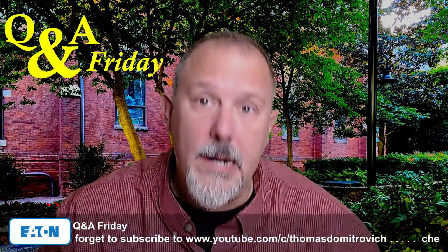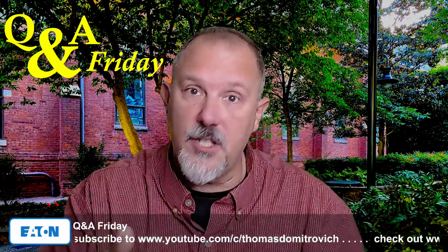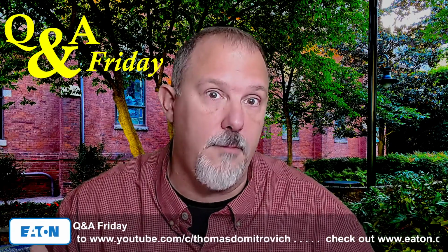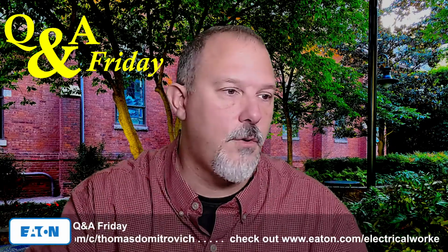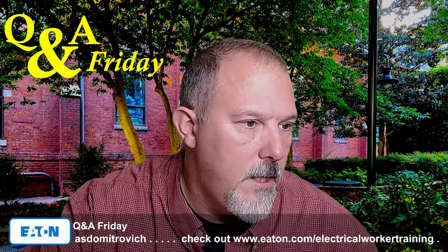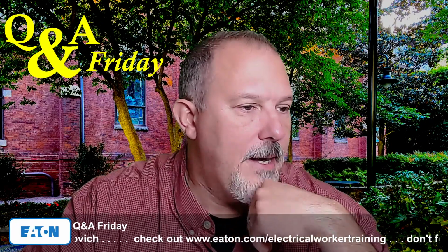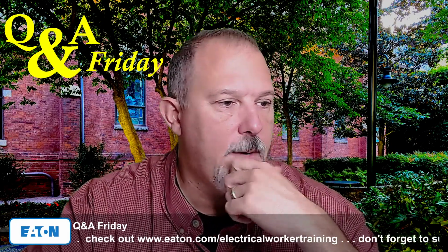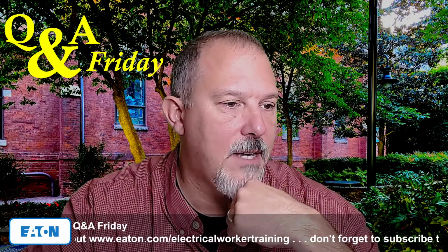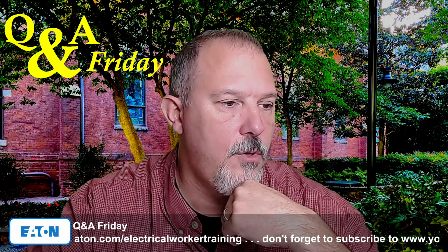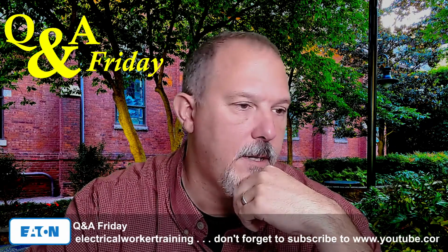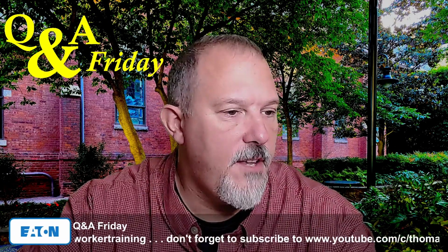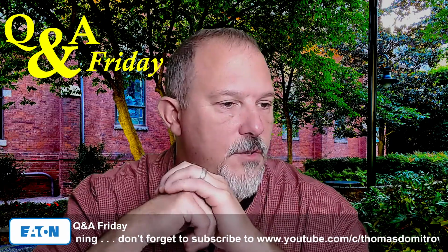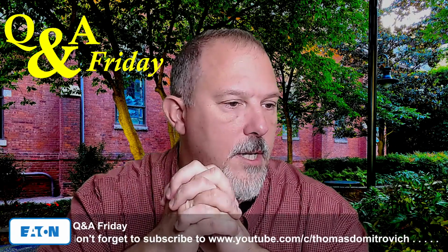And sometimes the breaker will get you there. If it's a current limiting circuit breaker, which we do make, you can use the same process if you're using your circuit breakers. All right. One example: equipment rated 5,000 SCCR, 8,000 amp fault current available. Use current limiting fuses to protect the equipment. Sorry if you addressed this, but can't a current limiting fuse be used to lower the available fault current? We have done this for equipment. I'm curious if this can be done for panels.